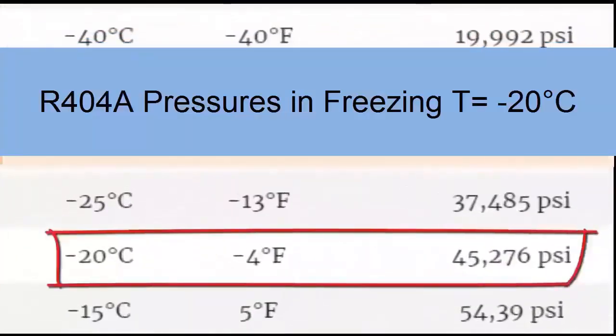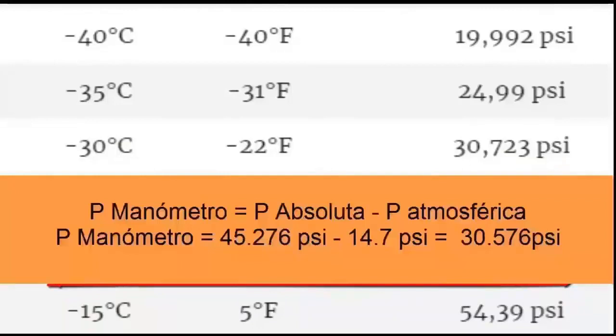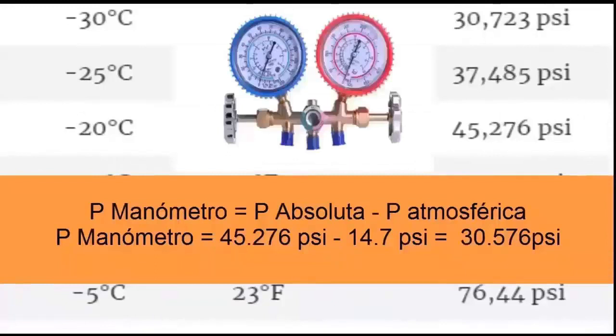Low pressure present in freezing equipment for an evaporator temperature of minus 20 degrees Celsius, about minus 4 degrees Fahrenheit. Here we have an absolute pressure of 45.276 psi. To know the low or evaporator pressure that the manometer would mark, we subtract the atmospheric pressure from the table value. In this way, 45.276 psi minus 14.7 psi is obtained, resulting in a gauge pressure value of 30.576 psi.